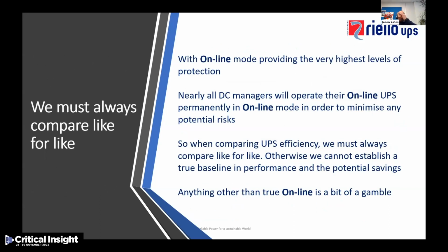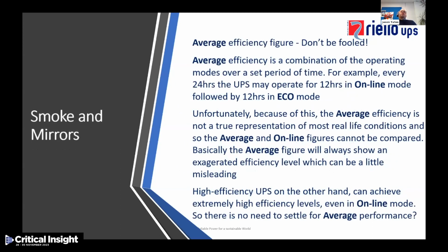Now, an online UPS system provides the very highest levels of protection, and nearly all DC managers will operate their online UPSs permanently in online mode in order to minimize any potential risks. So when comparing UPS efficiency, we must always compare like for like. Otherwise, we can't establish a true baseline in performance and the potential savings that can be achieved through high efficiency. Anything other than true online can be a bit of a gamble to a DC manager. A lot of the time you'll hear the term bandied about of an average efficiency figure. You've got to be careful with this, because an average efficiency figure is not the same as an online figure. Average efficiency is typically a combination of those operating modes we were just talking about.